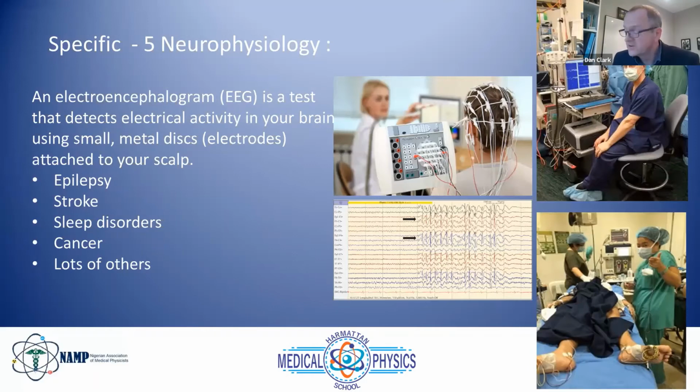Because the brain is a sphere, what we try to do is we put electrodes onto the skin of the scalp, and you can see in the photograph, I hope, in a sort of net, which arranges them at very specific points around the head, and we feed them back into a piece of instrumentation, which is sometimes referred to as a head box, and each of those signals from those different transducers comes back into that head box. Some very sensitive high impedance front-end amplification. If you're an electronic engineer, you'd love finding those because it's quite a challenging thing to design.